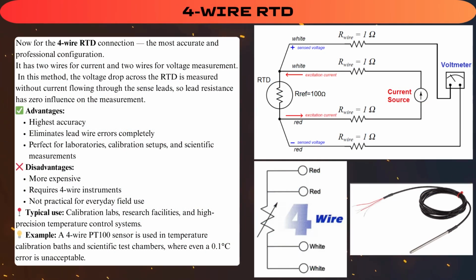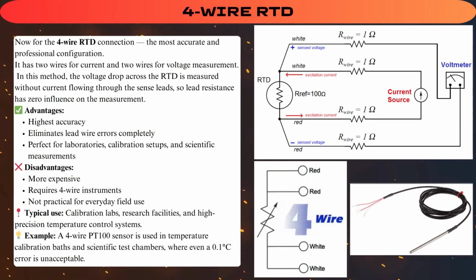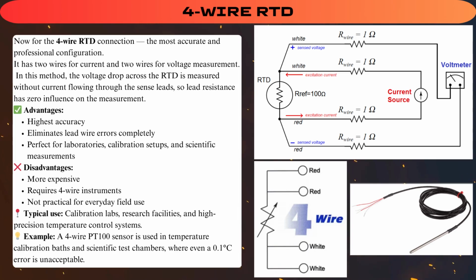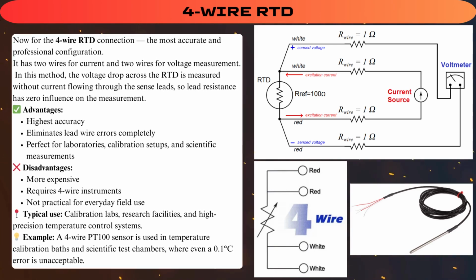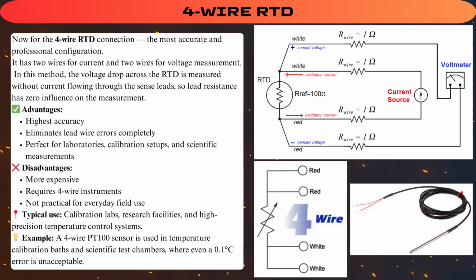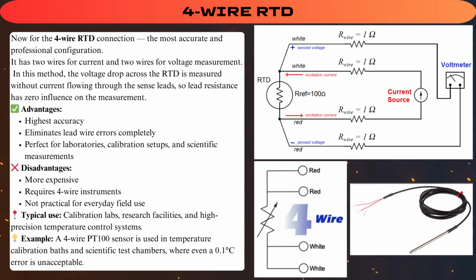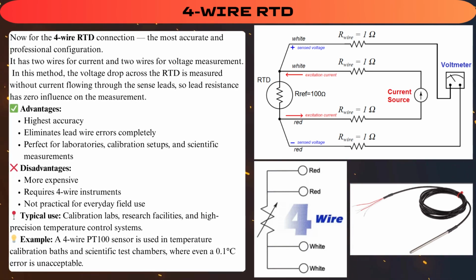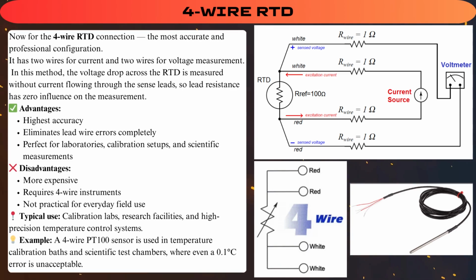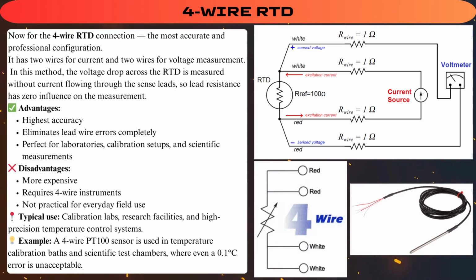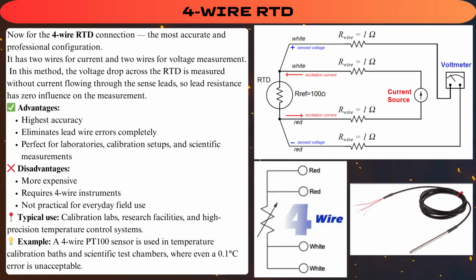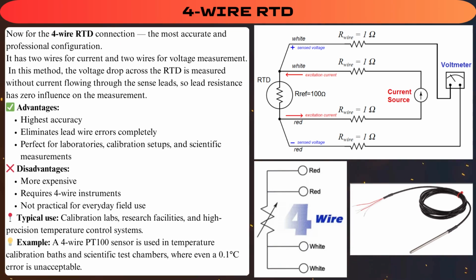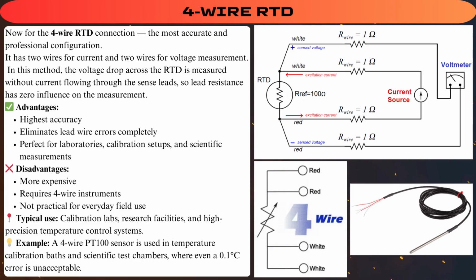4-wire RTD. Now for the 4-wire RTD connection, the most accurate and professional configuration. It has 2 wires for current and 2 wires for voltage measurement. In this method, the voltage drop across the RTD is measured without current flowing through the sense leads, so lead resistance has 0 influence on the measurement.